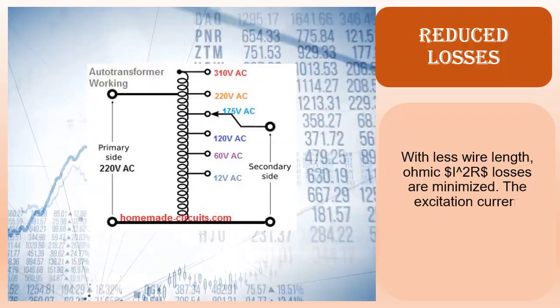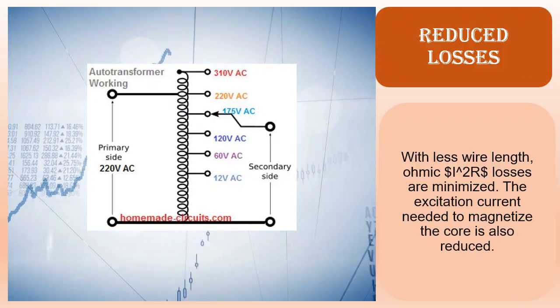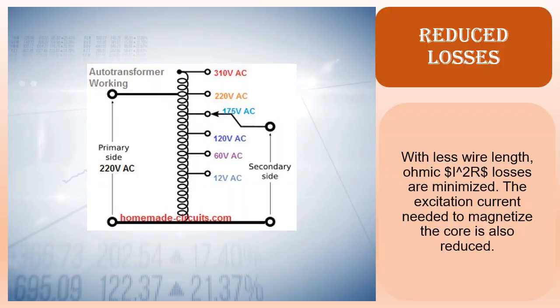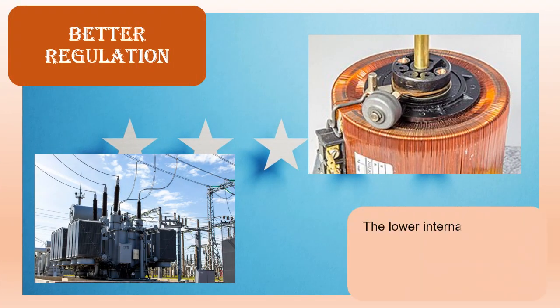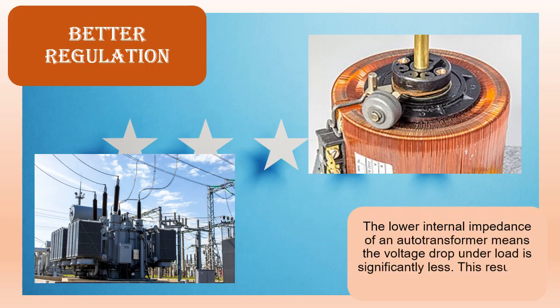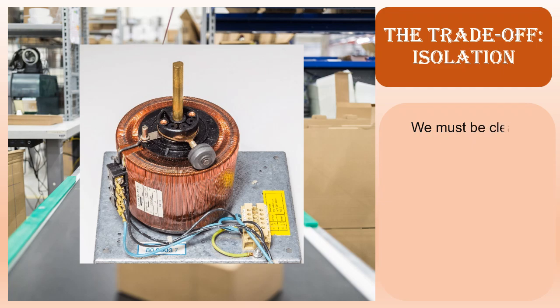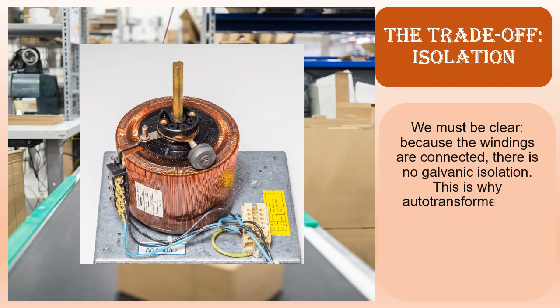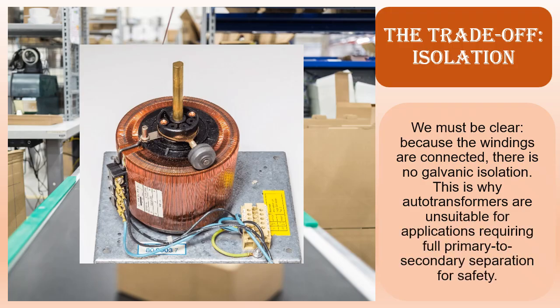The trade-off, isolation. We must be clear, because the windings are connected, there is no galvanic isolation. This is why autotransformers are unsuitable for applications requiring full primary to secondary separation for safety. The verdict. When you need a slight voltage step up or step down and isolation isn't mandatory, like stepping 480 V down to 460 V for a motor, the autotransformer is the far more economical and efficient choice.